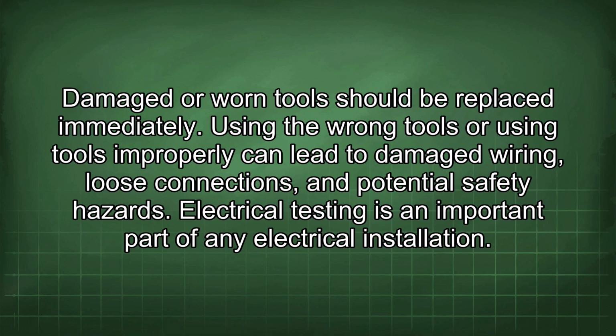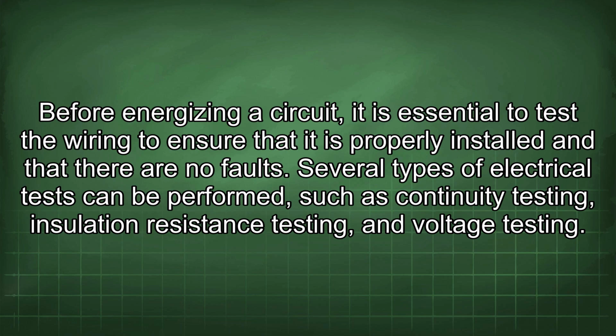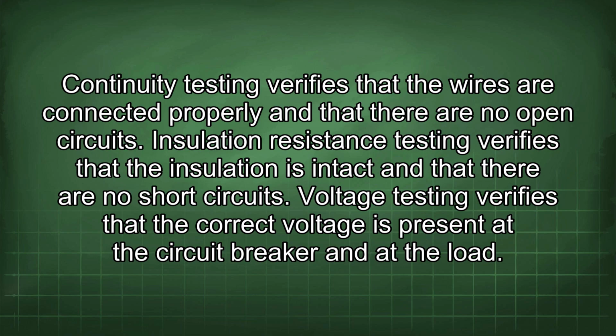Electrical testing is an important part of any electrical installation. Before energizing a circuit, it is essential to test the wiring to ensure that it is properly installed and that there are no faults. Several types of electrical tests can be performed, such as continuity testing, insulation resistance testing, and voltage testing. Continuity testing verifies that the wires are connected properly and that there are no open circuits. Insulation resistance testing verifies that the insulation is intact and that there are no short circuits. Voltage testing verifies that the correct voltage is present at the circuit breaker and at the load.